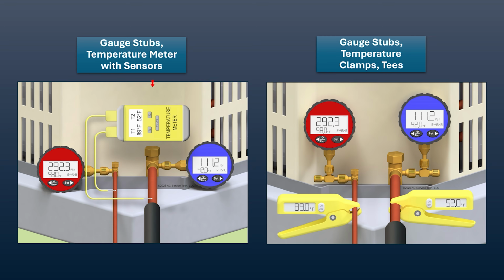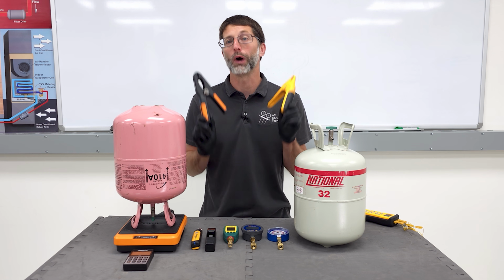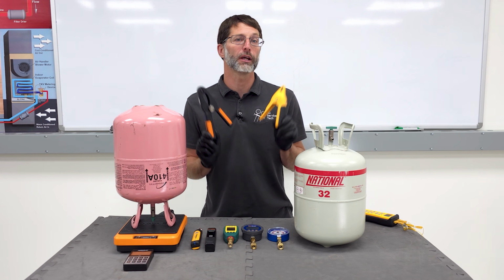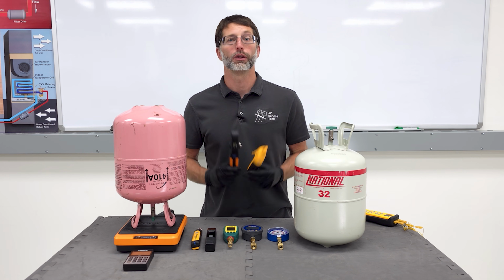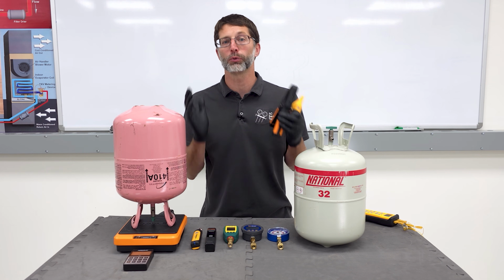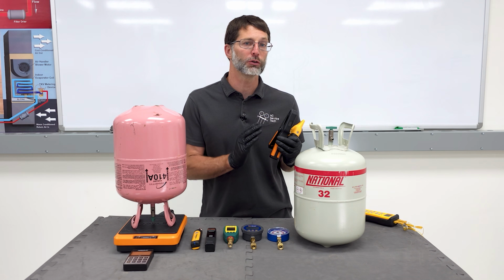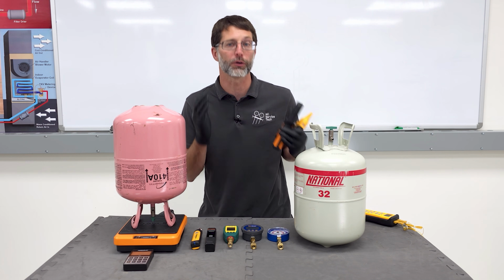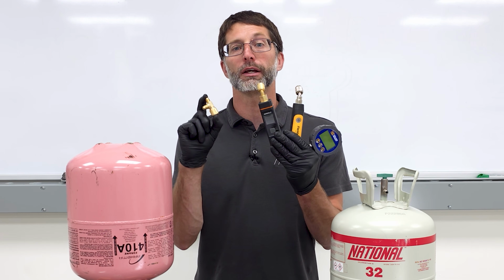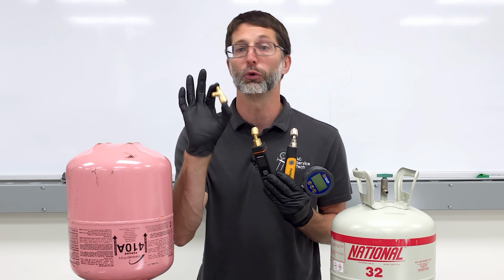or probe instead. A digital temperature meter with temperature sensors, see figure 4-43, digital temperature clamps, see figure 4-44, or wireless temperature clamps can be used in conjunction with gauge stubs. The use of gauge stubs or wireless probes allows for a quick connection to and disconnection from the system ports. These tools can be used in conjunction with an access tee for refrigerant charging.